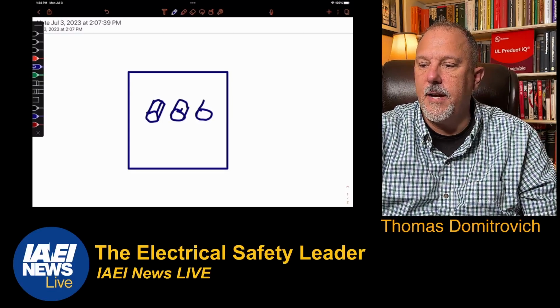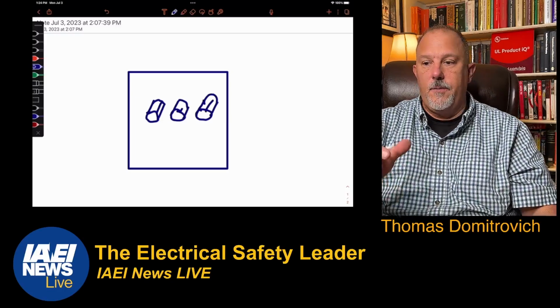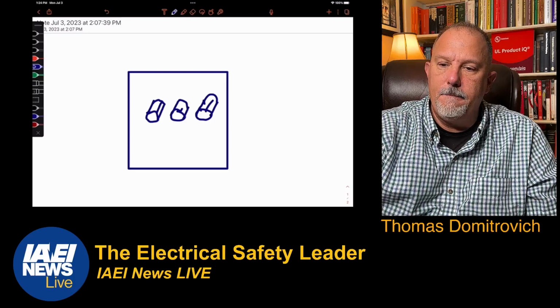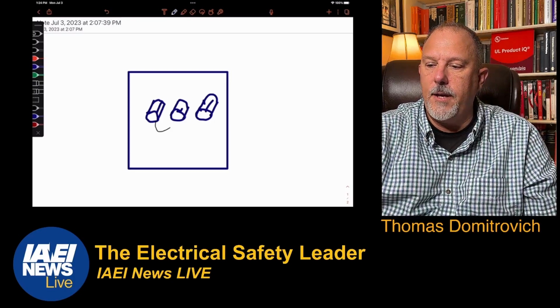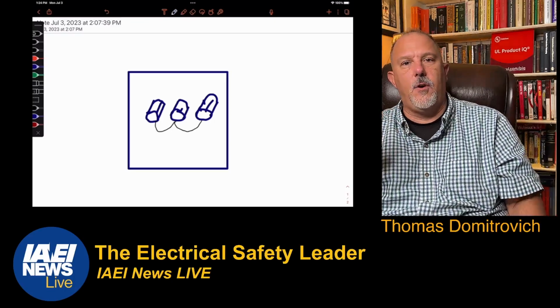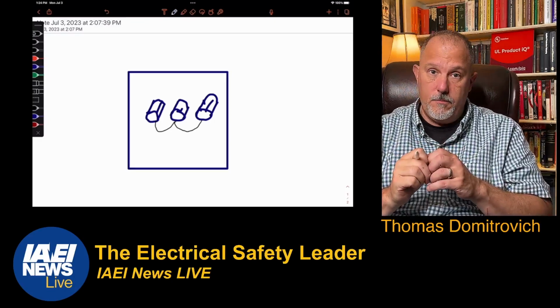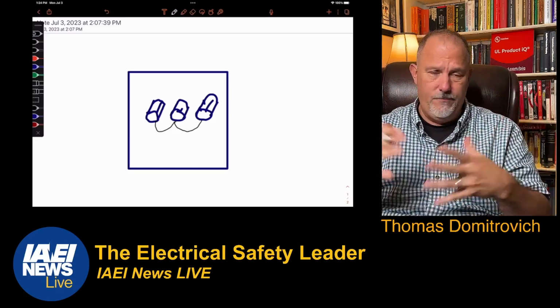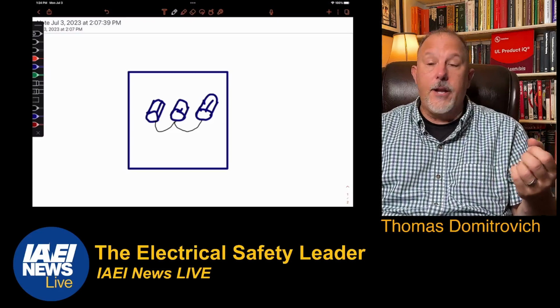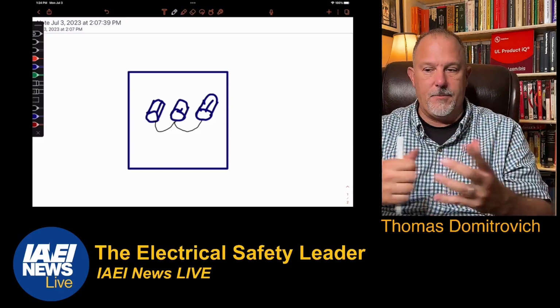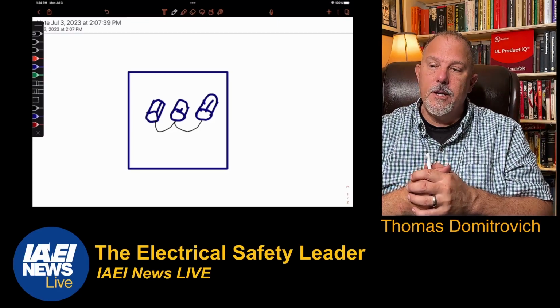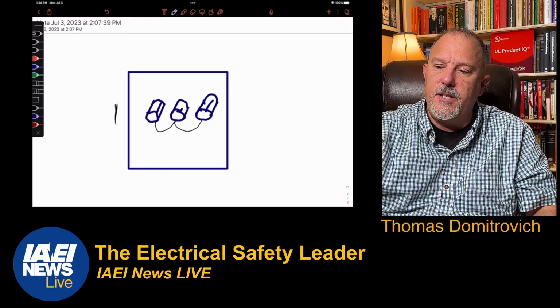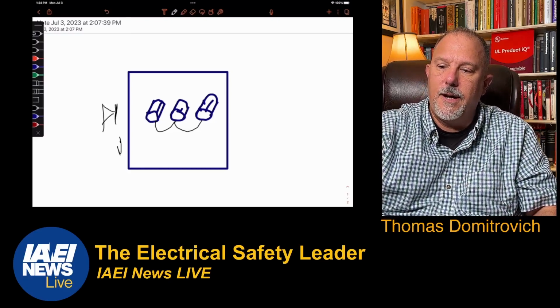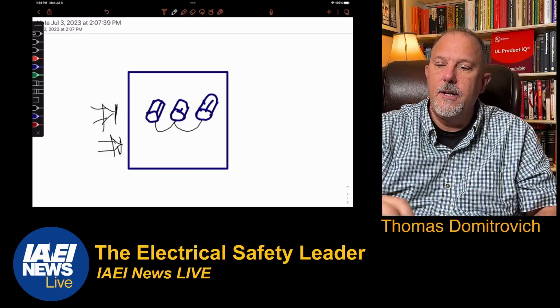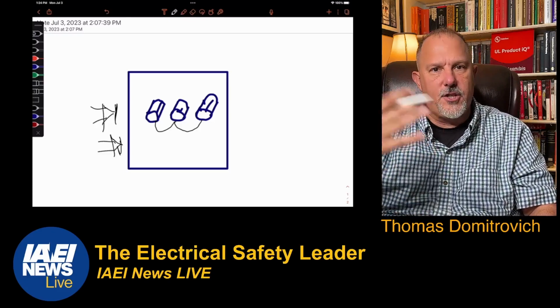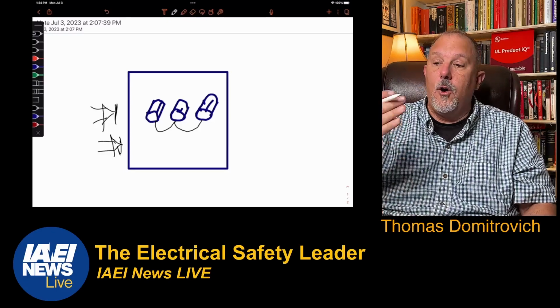Boy, we're testing my drawing capabilities. Imagine he's looking at you. Then we take a wire and we connect each of these together. It's a very small initiation. We know it's going to act like a fuse in air, and it'll initiate the arcing fault and create that plasma cloud that we're talking about. Then on the front, we put these sensors. I don't know how to draw a sensor. We'll just draw it like that. And we measure the heat that's generated at so many inches away, say 18 inches away from the event.